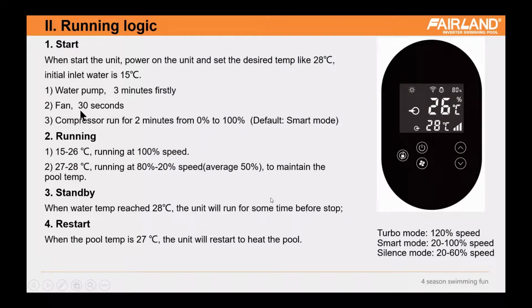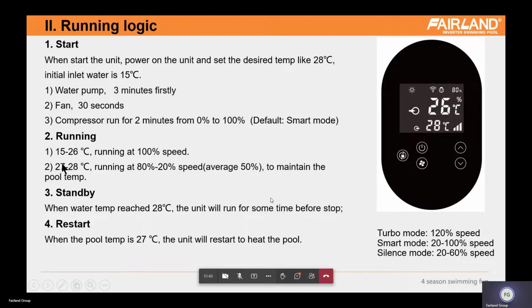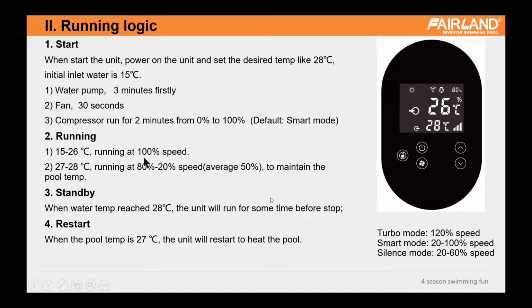After the fan runs for 30 seconds, the compressor will run for 2 minutes from 0% to 100%. Here you can see the running percentage rises smoothly from 0 to 100%. So after almost 6 minutes, the heat pump works with full power normally. And before 27 degrees, the unit will always keep running at 100% to heat the pool temperature fast and get close to the desired temperature.